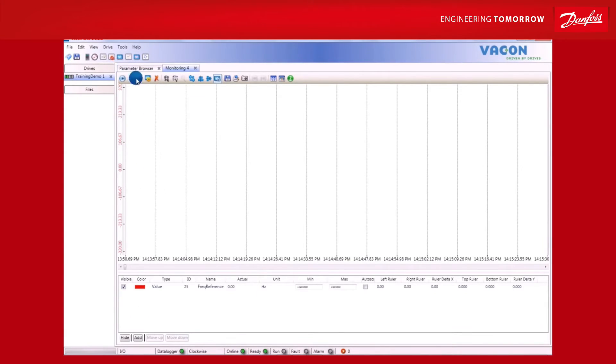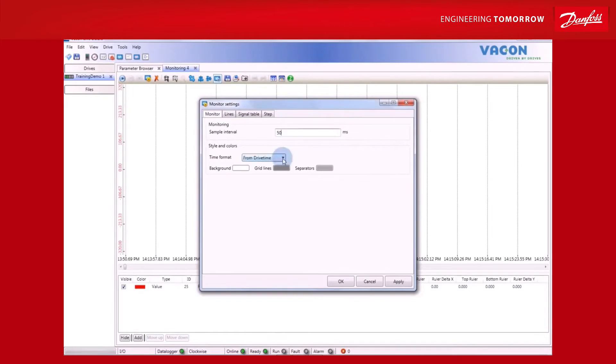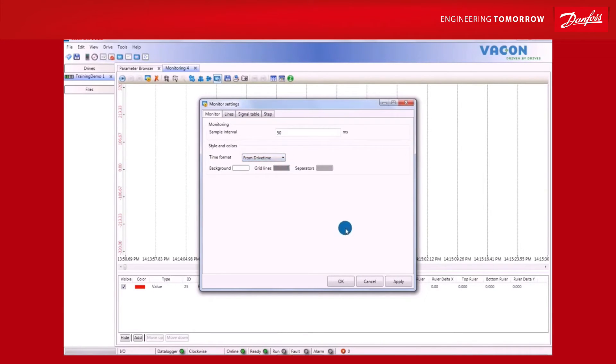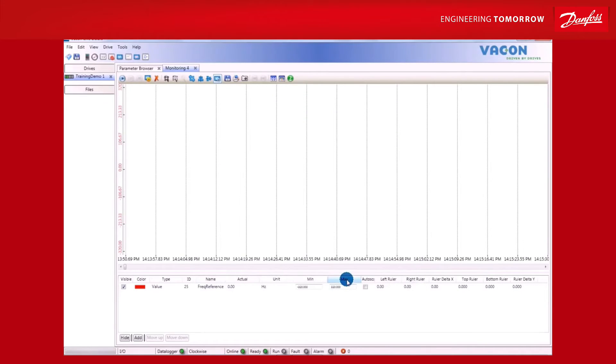Through VaconLive, you can view monitoring trends for set periods of time. It's easy to do. Simply open the monitoring window, go to Settings, and set a suitable sampling interval and time format. It can either run in real-time, known as drive time, or start from zero when the monitoring begins.